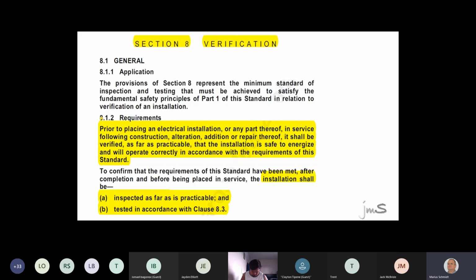Right. What's very important, I don't think this will be in your exam, but it's definitely in the regs exam. When you install cables, if there's no bulk insulation yet, you must assume there's going to be bulk insulation installed. So at the end, it's still the sparky's responsibility to ensure that those guys who put the insulation in do it properly, because if they put insulation on both sides, you reduce the current rating of the cable. You must make sure that they put the insulation only on one side. Otherwise, the cable's going to burn and you're going to have a fire. So the moral of the story is, you do tests prior, during, and after everything is connected. How's that sound? Continuously.